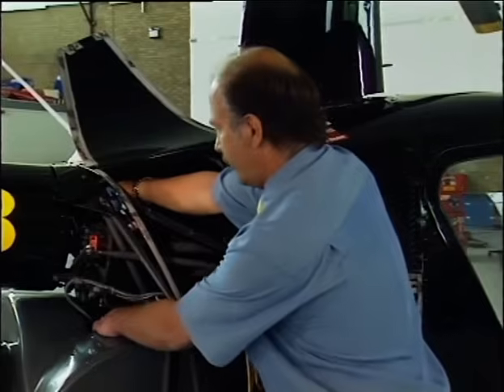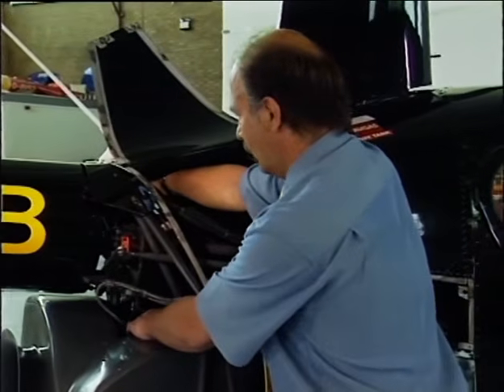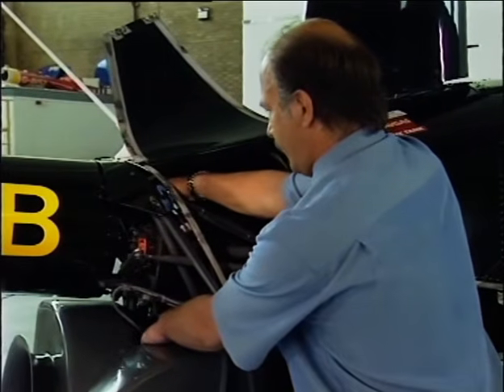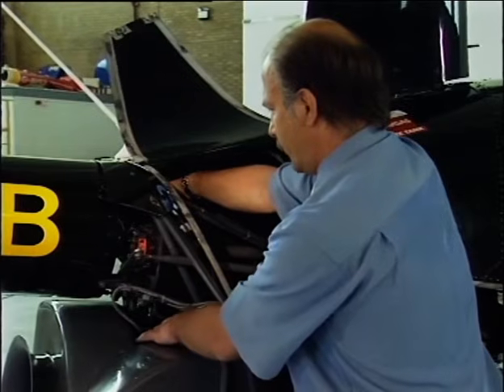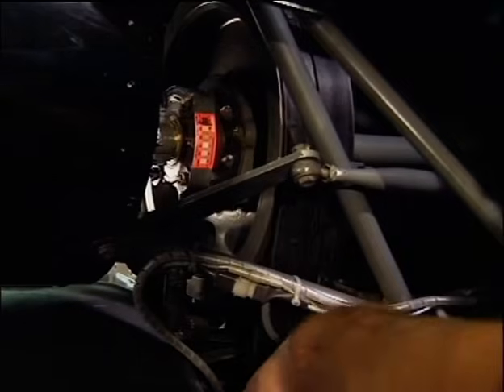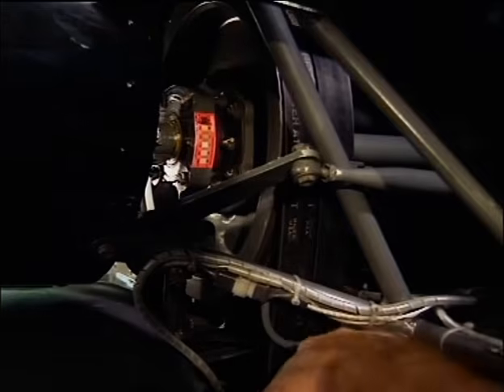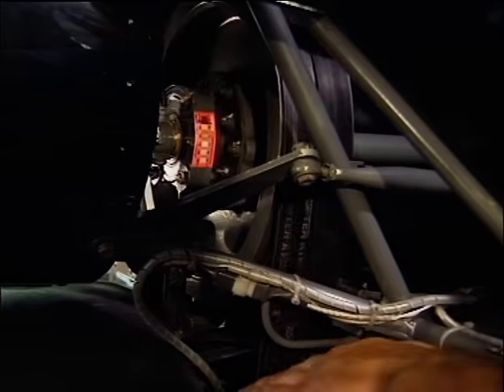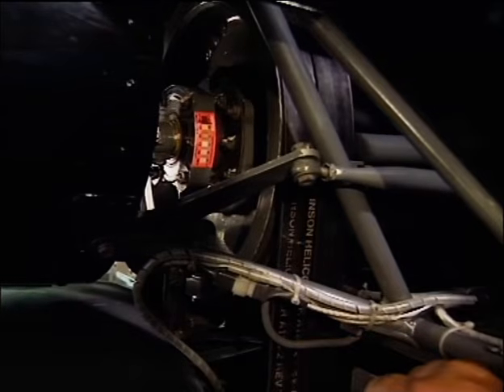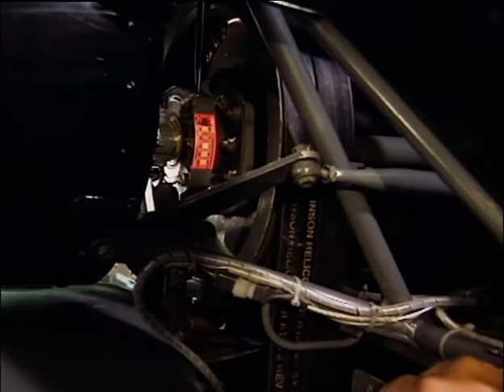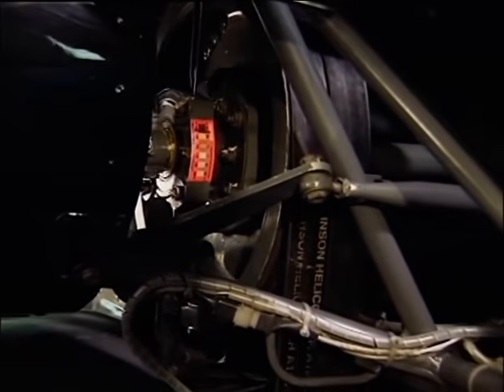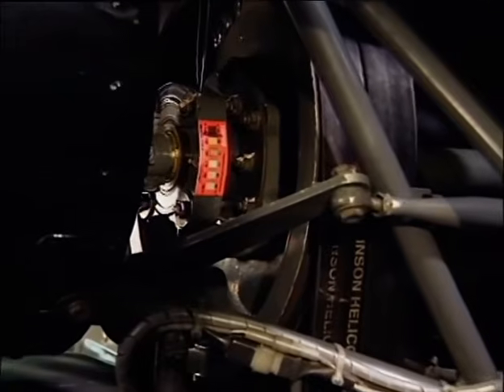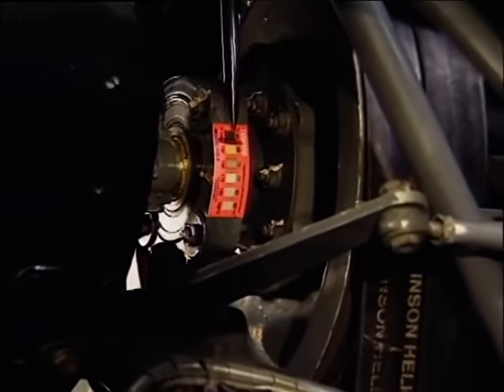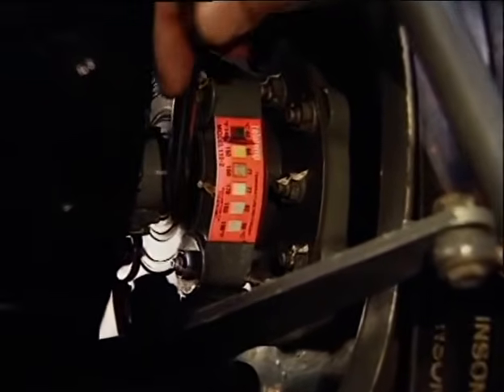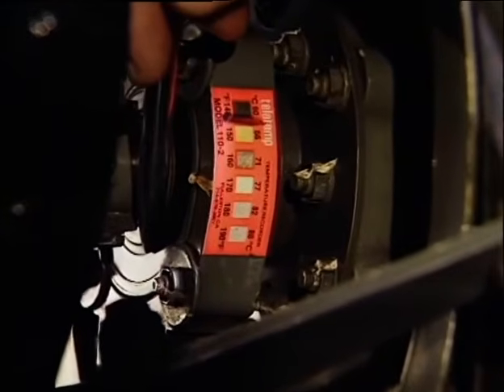We come on to the drive belts. We need to check for damage of the drive belts. If we push the belts in just here and rotate the upper sheave towards us, looking for nicks, cuts and frayed edges. Then coming aft, we have the upper sheave bearing. This is a ball bearing running in grease. If this bearing gets hot, the grease is going to melt and dribble from the seal just here.